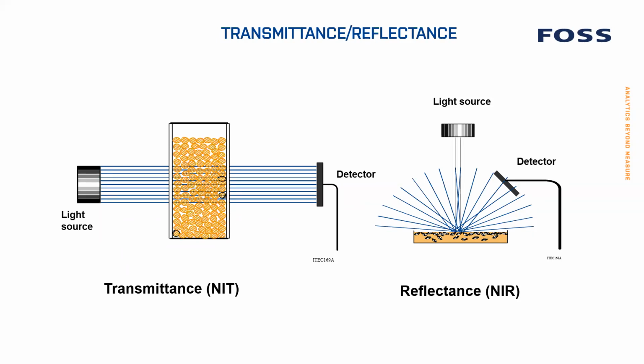For reflectance, we look at the surface. There it's more important that you actually have a homogeneous sample, so you need to grind it or mix it in some way so you get a more homogeneous sample. Then you look at the surface, and it doesn't penetrate very deeply, so you must be sure that the surface is representative of the sample. In our case, transmittance is typically used in Infratecs and FoodScans, where you have these inhomogeneous samples like grains and meat, while reflectance is mainly used for solid samples where you mill the sample and have some type of powder.